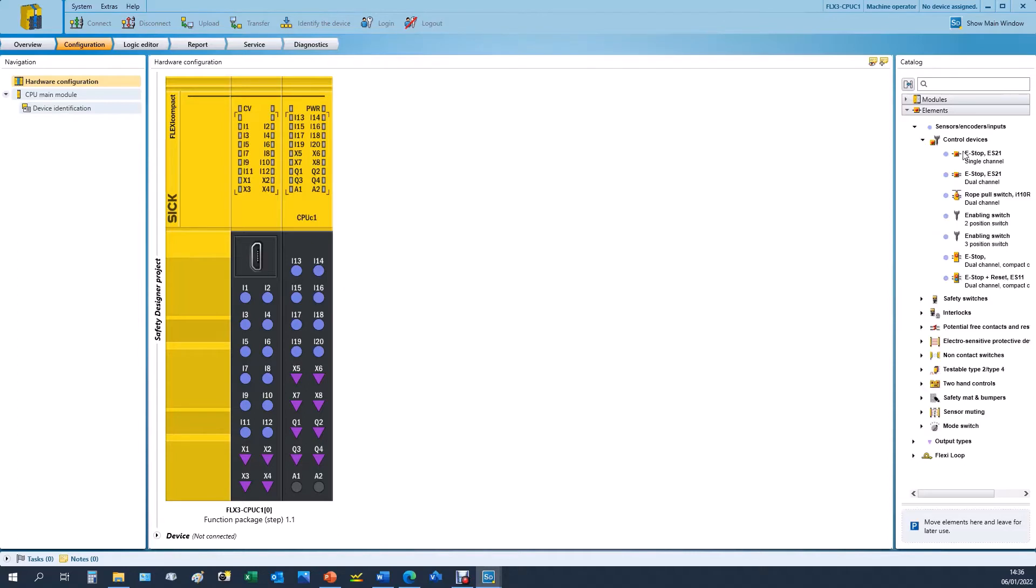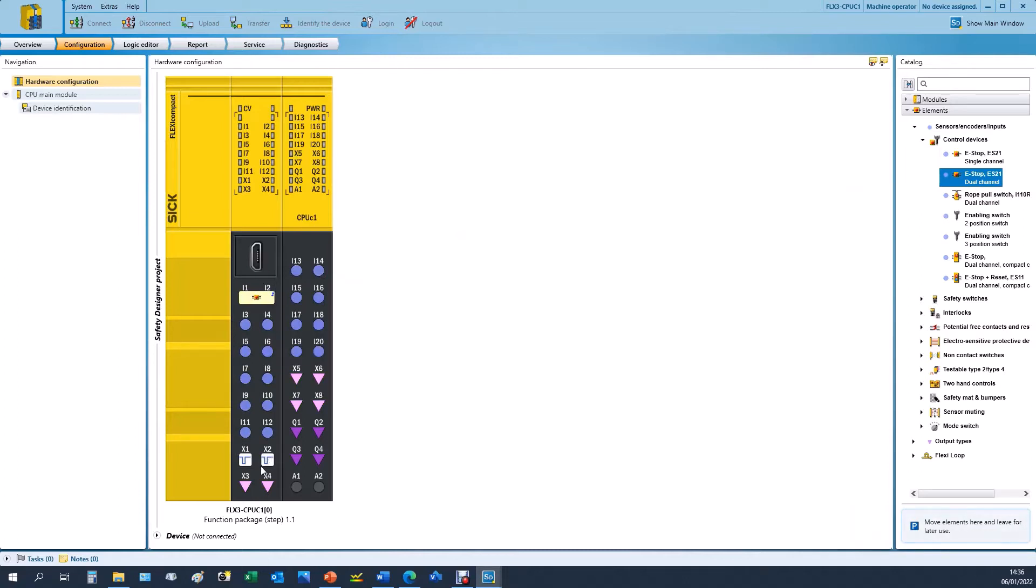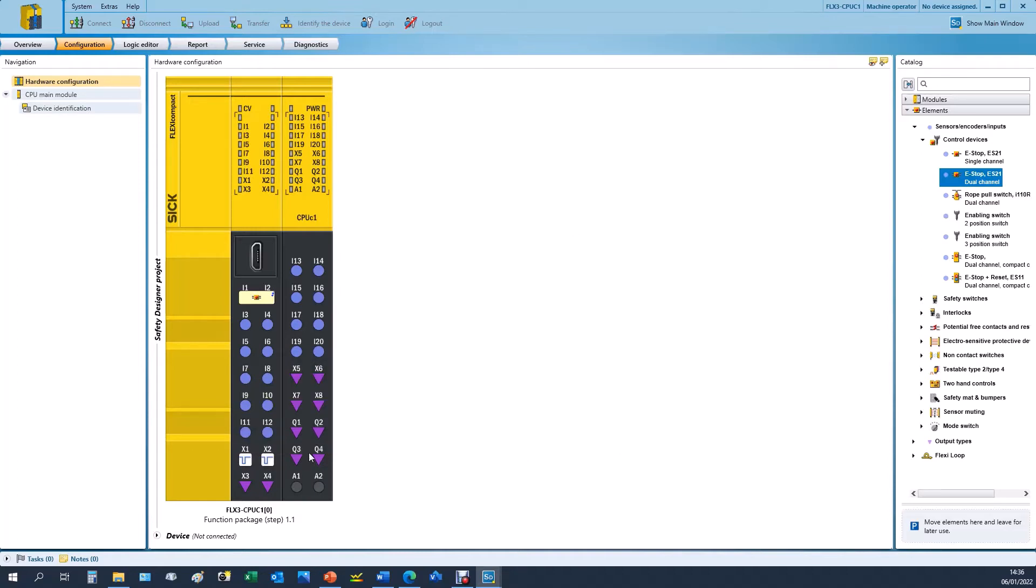For the e-stops you can find under control devices where we'll add a dual channel e-stop with test pulses. When you drag them to the inputs, which are the round blue circles, if it has test pulses it will also occupy two of the standard outputs which are designated with X with test pulses. If you want to know the duration and time periods of those, you double-click the icon and we can see we have a test period of 200 milliseconds with a test gap of 2 milliseconds for each channel of that e-stop. The Q denotes the safe outputs.